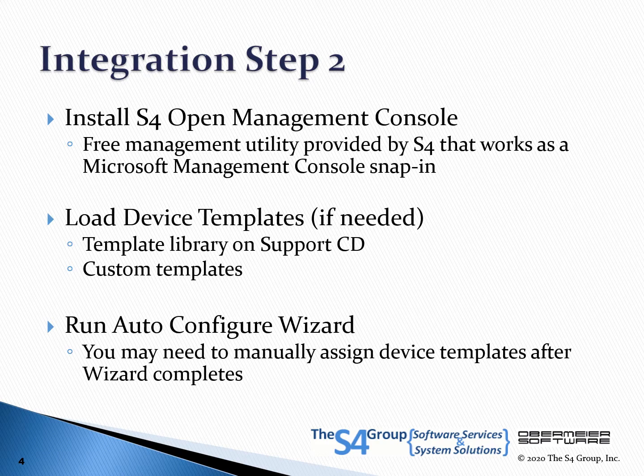Set the BACnet address for the N2 router and the virtual BACnet network number that will host the emulated BACnet IP devices representing each N2 device. Run the Configure Wizard. Assign any templates requiring manual attention. Validate that you are receiving correct data through BACnet.